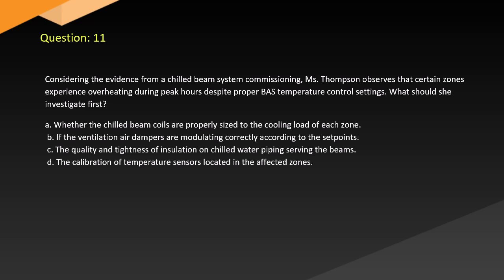Question 11. Considering the evidence from a chilled beam system commissioning, Ms. Thompson observes that certain zones experience overheating during peak hours despite proper BAS temperature control settings. What should she investigate first? A. Whether the chilled beam coils are properly sized to the cooling load of each zone. B. If the ventilation air dampers are modulating correctly according to the set points. C. The quality and tightness of insulation on chilled water piping serving the beams. D. The calibration of temperature sensors located in the affected zones.